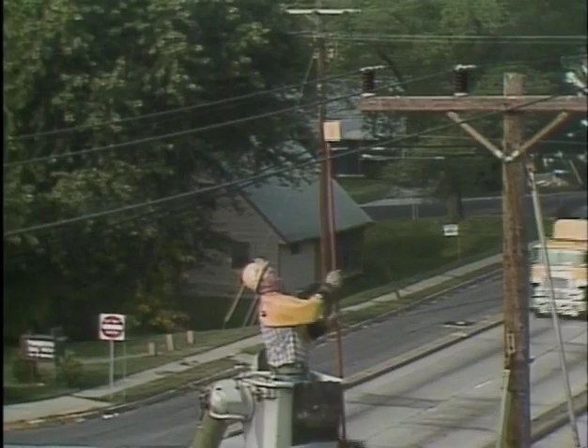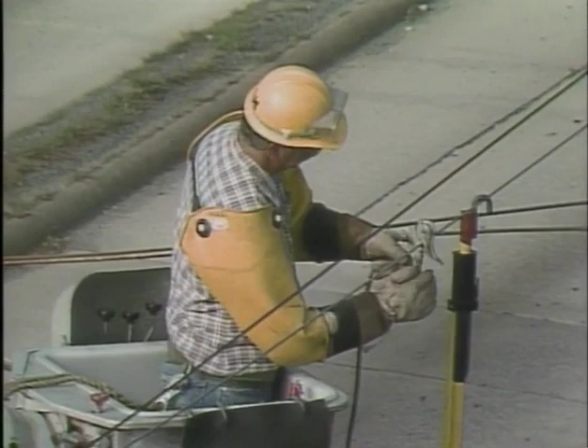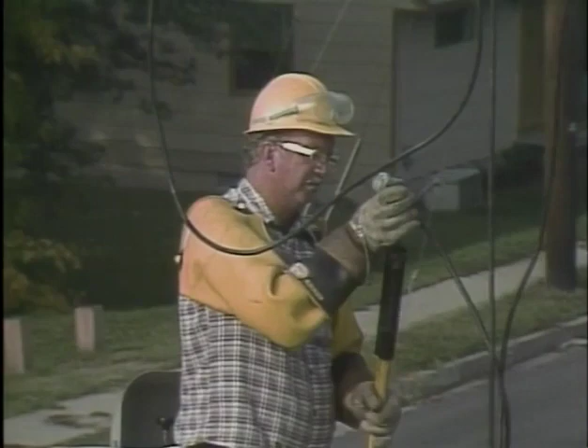To install a temporary ground, you must first test the circuit to make sure it's de-energized. Grounding an energized circuit is a serious hazard. These grounds are designed to be applied only when a circuit has been de-energized. In this example, one end of the jumper cable is attached to an established ground. The other end of the jumper is attached to the center conductor wire. Each of the other conductor wires is attached by jumpers to the center conductor wire. This creates one electrical path to ground for all 3 of the conductor wires. Now the worker can complete the maintenance on the lines safely.